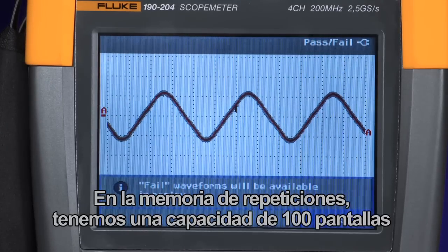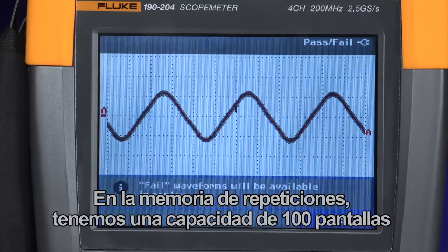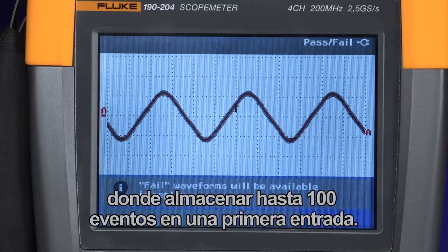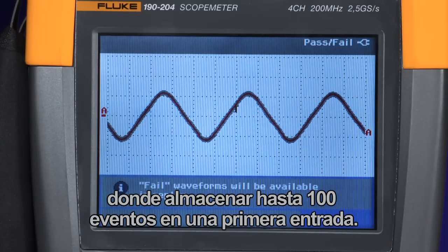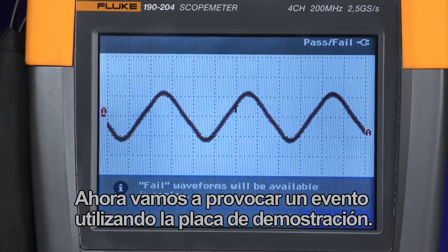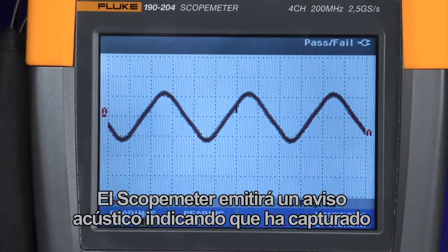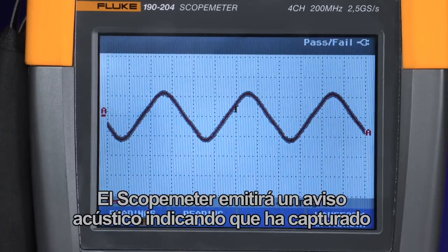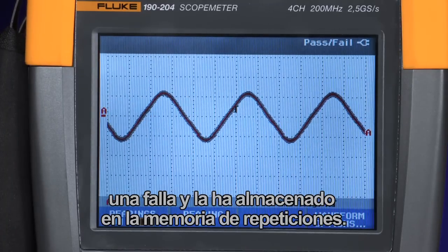For this test, we'll choose store on fail. Now the oscilloscope will monitor the input waveform and compare it to the waveform envelope that we've just created. Any time a trace falls outside of that plus two pixel window, it will immediately capture that screen and store it to the replay memory. In the replay memory, we have a buffer of a hundred screens where you can store up to 100 events on a first in, first out basis. Now let's cause an event using the demonstration board. The scope meter will beep indicating that it has captured a fail and stored it in the replay memory.